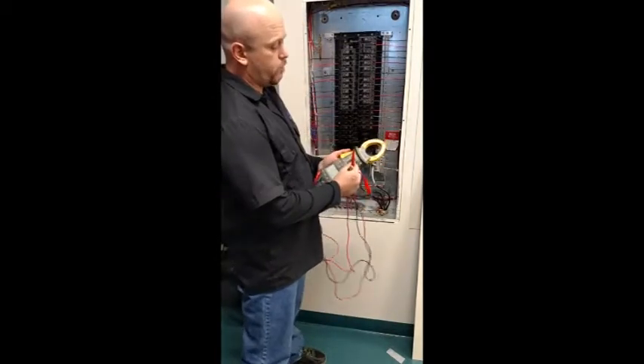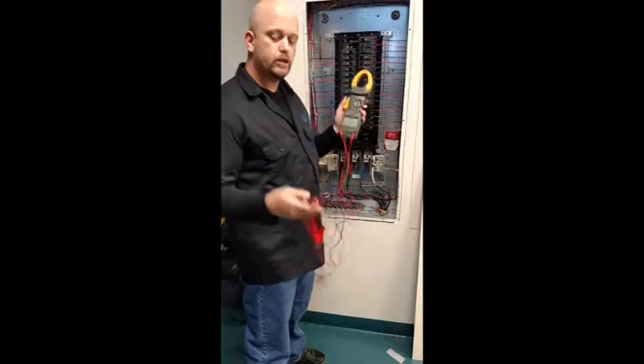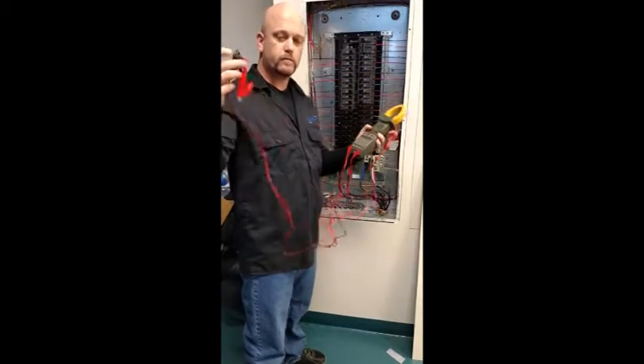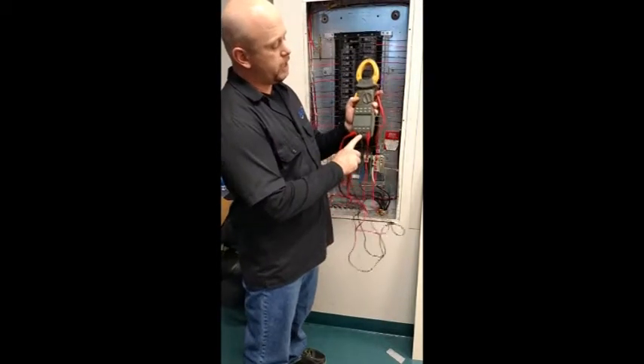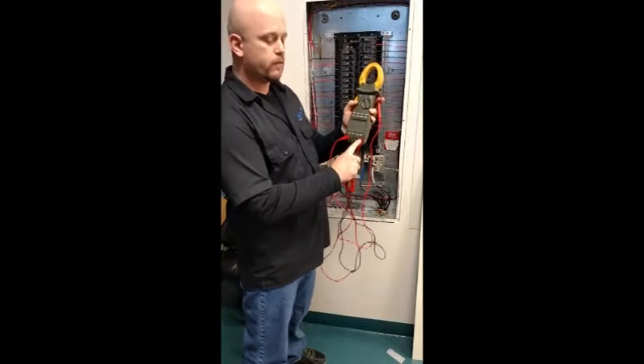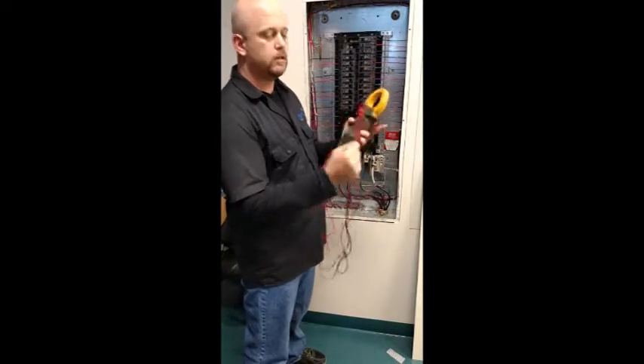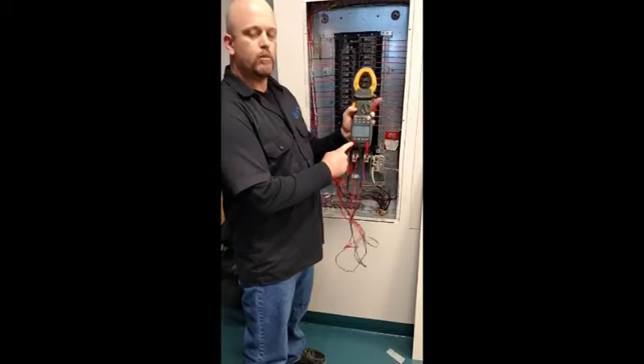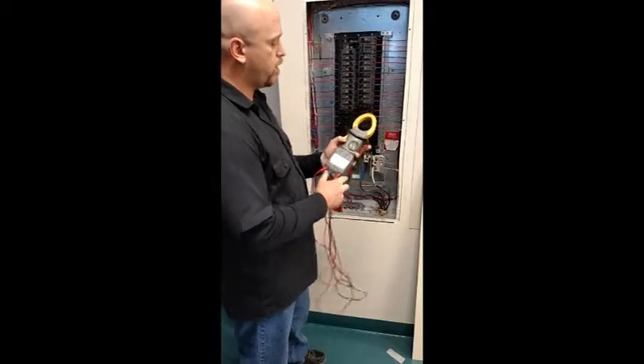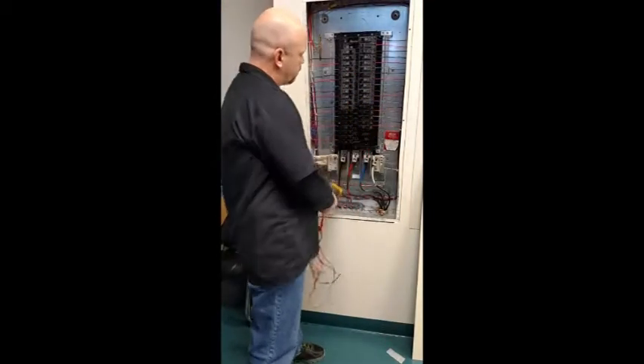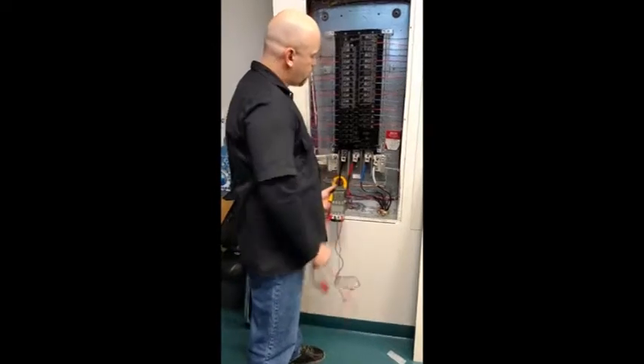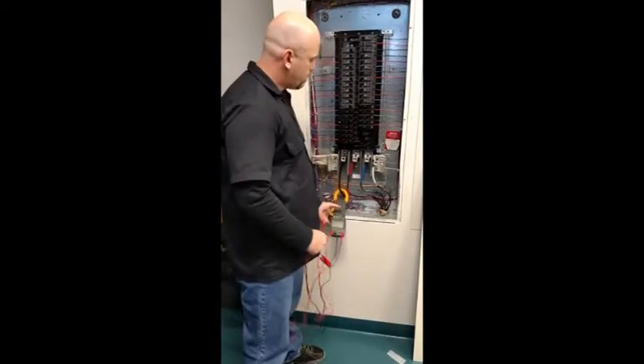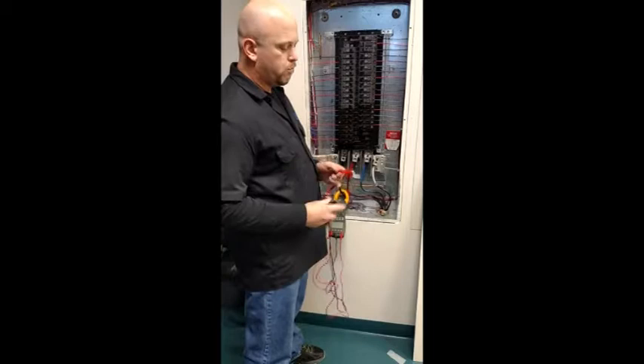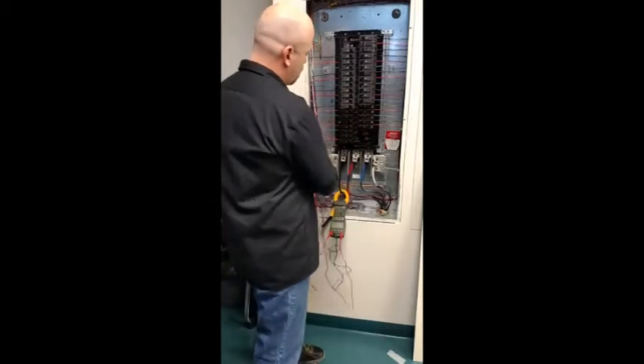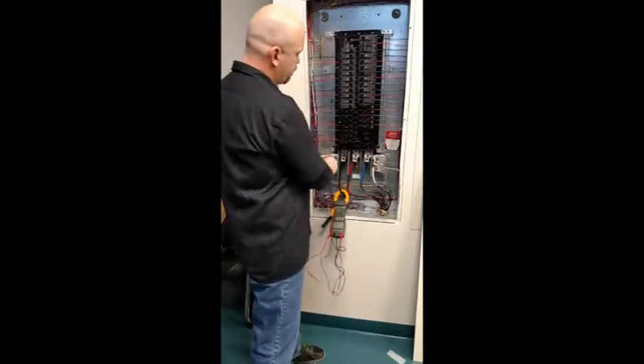The first option, we're going to need two clamps, and the two clamps will be in common, V2 and V3, and we'll need a probe, and we'll want that to be in V1 to do this three-phase four-wire Y testing. We will put our clamp around the primary leg. Both clamps, V2 common and V3, will go onto neutral.